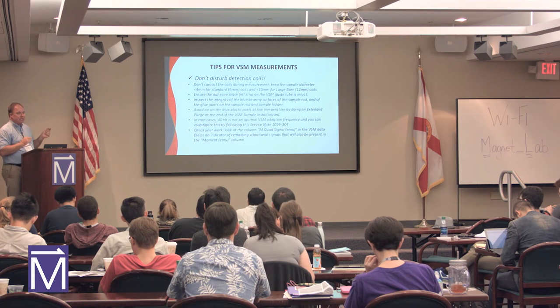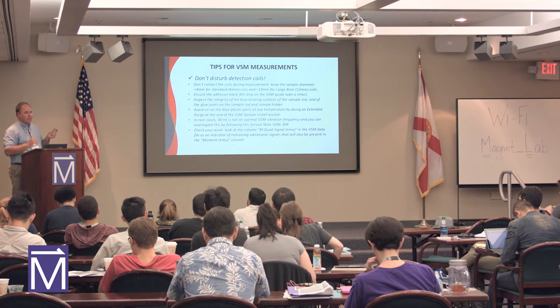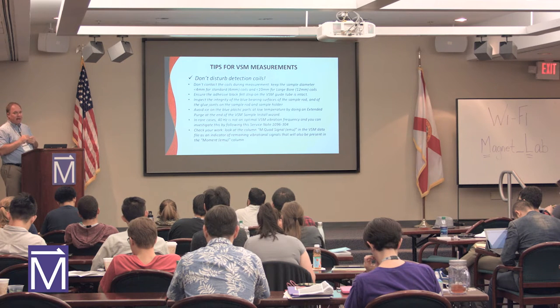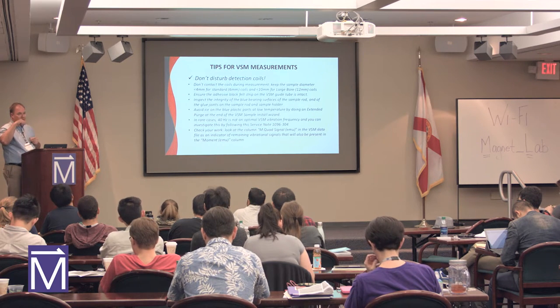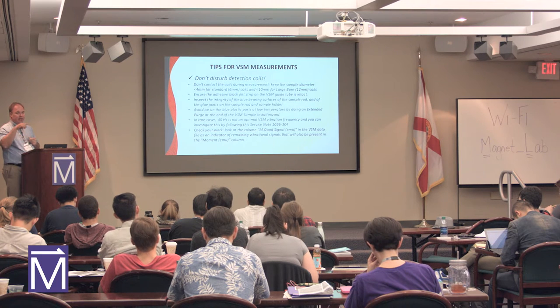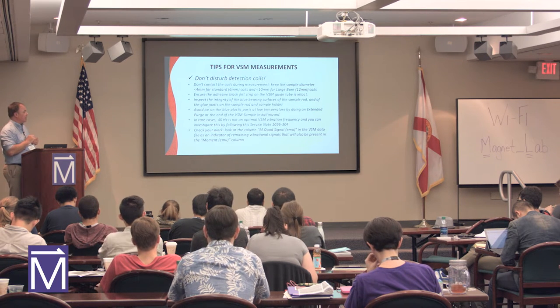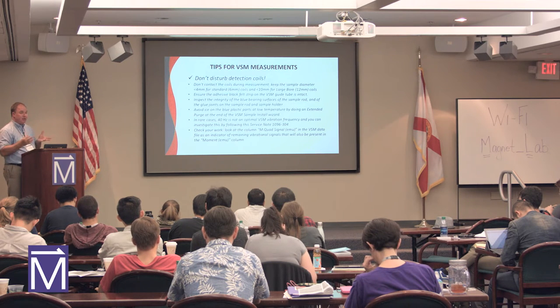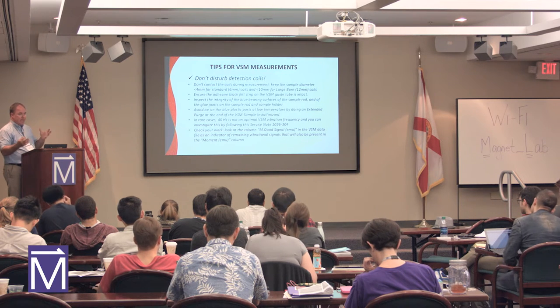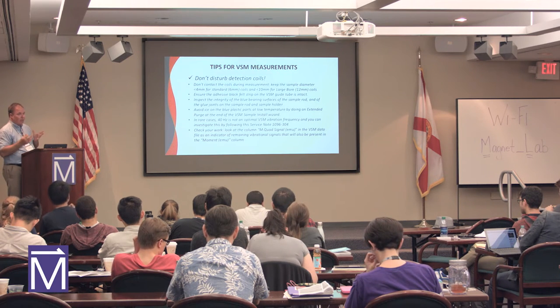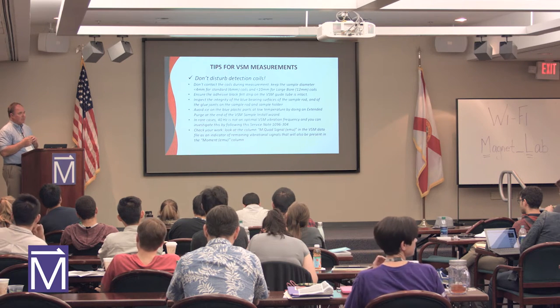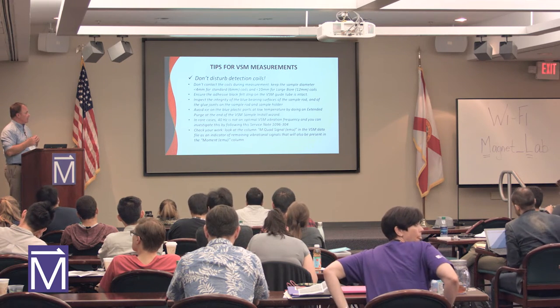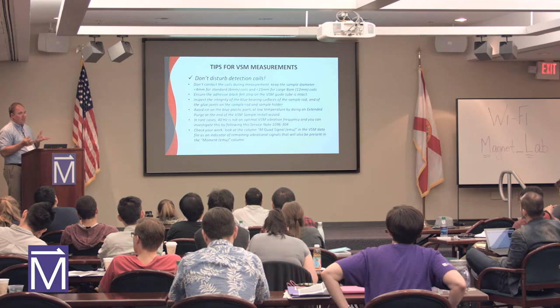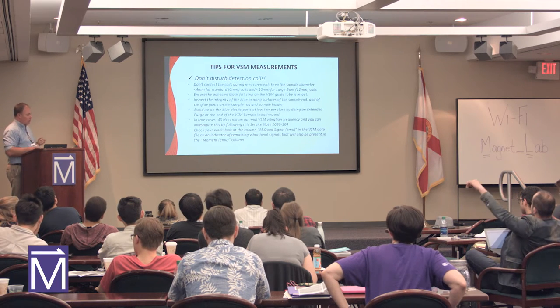The common source of this error is some ice that forms in the system. So you didn't purge the system out enough. Ice will form on a couple of the parts on the sample rod, and those will touch the coil and cause an artifact. So you need to make sure your sample's not outgassing, not absorbing atmosphere and then freezing into the system. Those are some things you may want to check, and check the high vacuum of the system so that there's no ice forming.